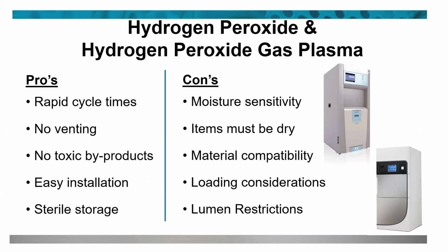Our pros are that we have rapid sterilization times, most often under 1 hour. There also are no environmental concerns because, again, it breaks down into water and oxygen, and the units only require electricity, so they're easy to place in different areas because you just have to have the electrical component.